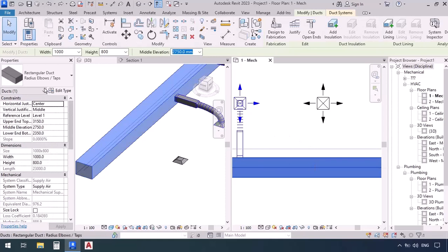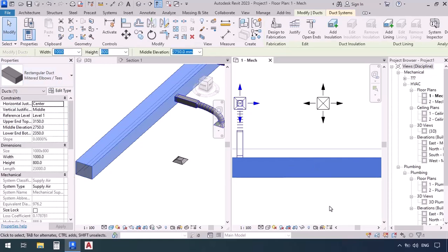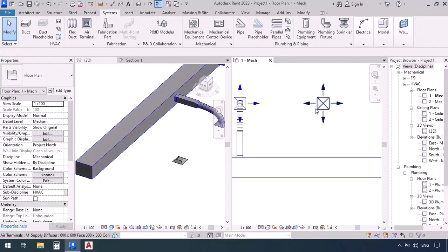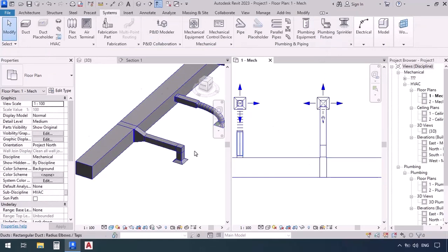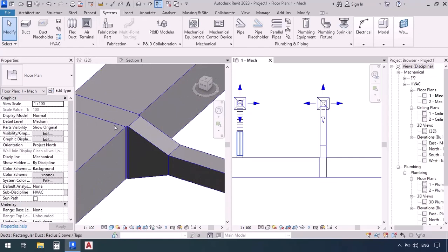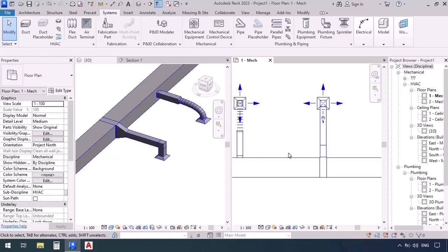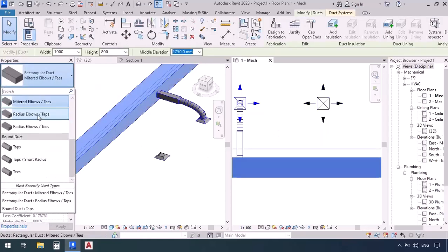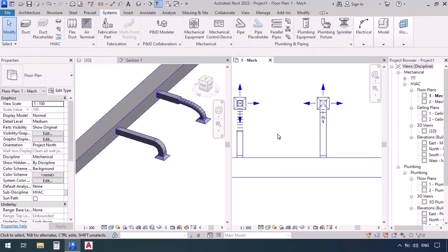Let's undo and try again. Click on the main duct and change its fitting type to mitered elbows T's. Now click on the terminal and connect it into this duct — you can see the mitered elbow. Because it was a mitered T, it applied a T for the connection, and because the size of the duct was different from the connection, a transition was also applied. It takes its properties and features from the original main duct. I'll press Ctrl+Z, select the duct, make its fitting radius elbows taps, then select the terminal and connect it into this duct.